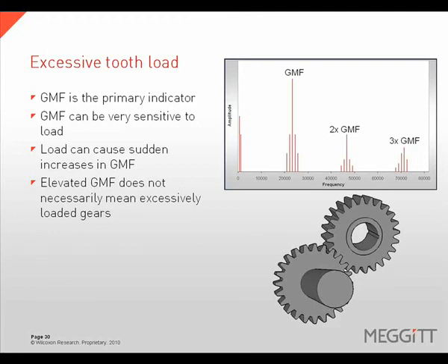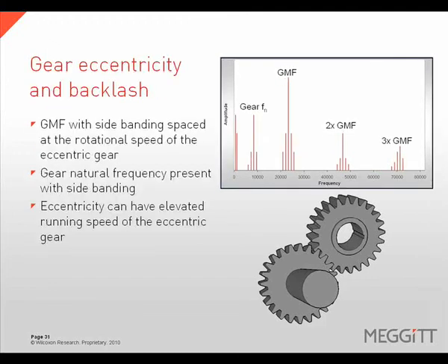Elevated gear mesh frequency does not necessarily mean excessively loaded gears. Gear eccentricity and backlash problems will create elevated levels of gear mesh frequency with sidebands spaced at the rotational speed of the eccentric gear. The gear's natural frequency can be present with sidebanding, and running speed harmonics of the eccentric gear can be elevated.